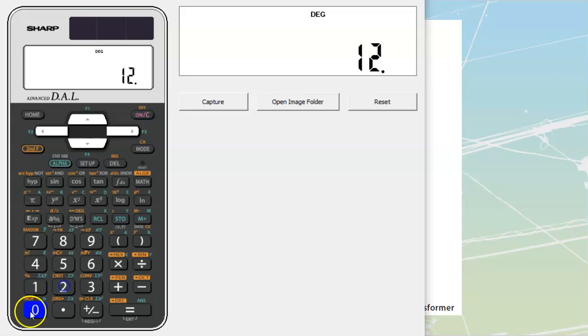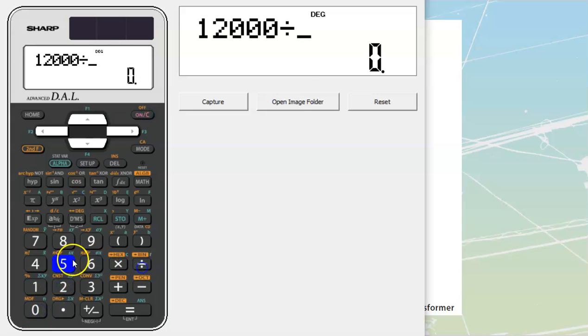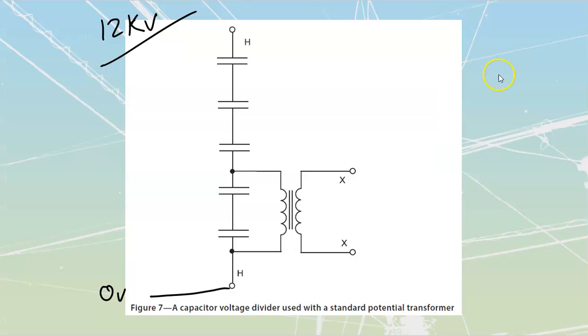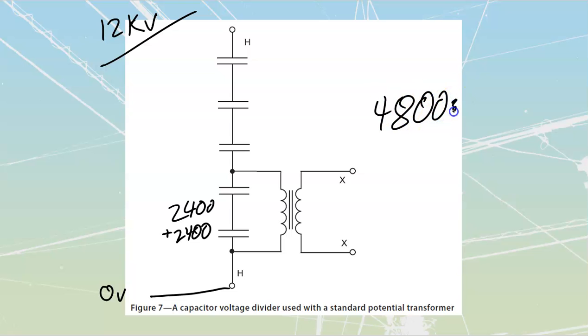We'll take 12,000 divided by 5, which gets us 2,400. So each of these caps now has 2,400 volts across it. What do I see over here? My PT is going across 2,400 plus another 2,400, so it's across 4,800. This means I'm only doing a voltage transformation of 4,800 down to 120 volts.